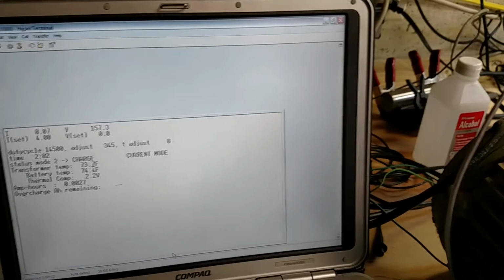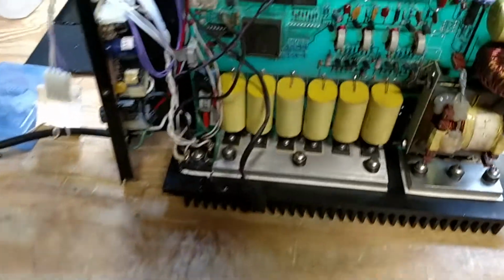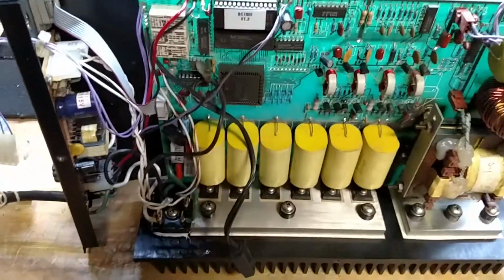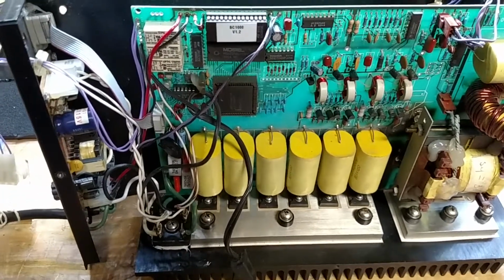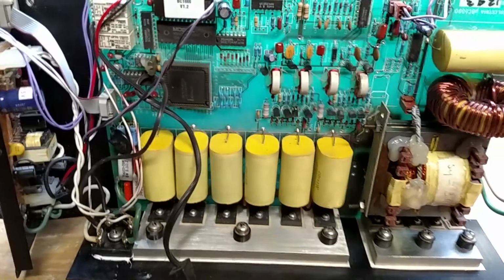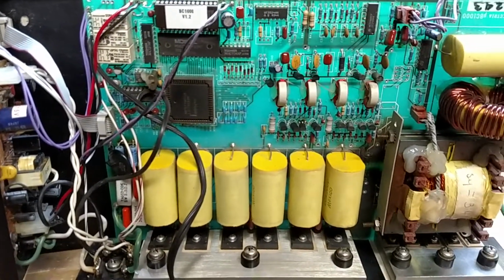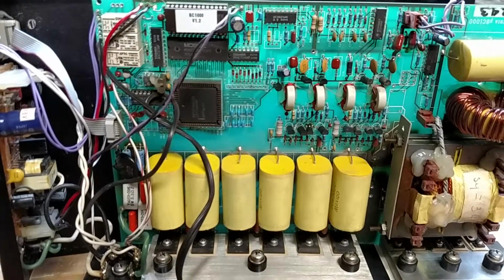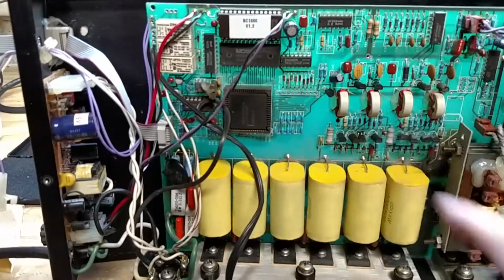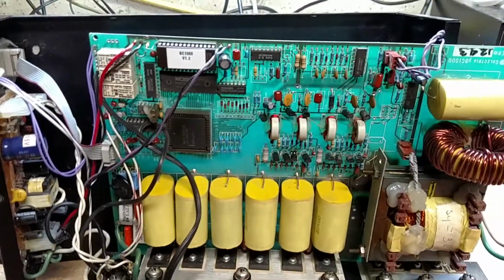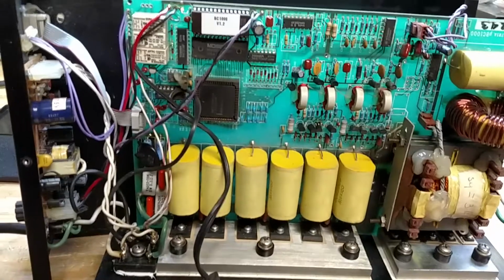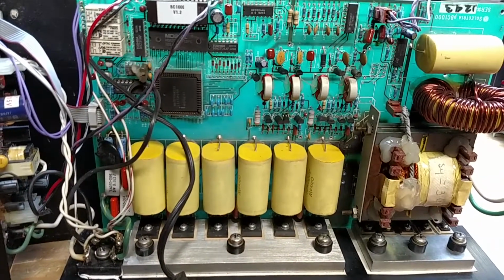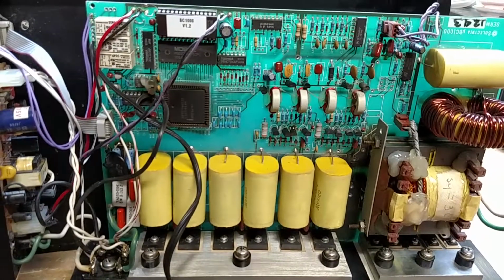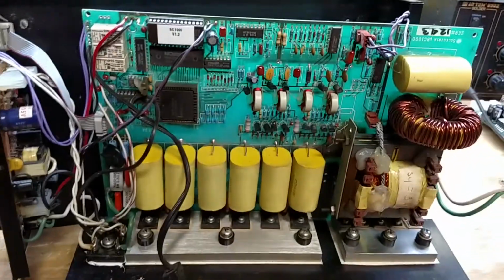So, as I suspected, at least we're talking now. Before we had no communications because there was no EPROM. So we're reading the code right now. But we have to do some more troubleshooting. We're powering it, everything's working, but we're not getting any oscillation. The transformer's not right, or the oscillator, something in here is probably dead. So we'll just have to look into it and do some troubleshooting. I don't see anything obvious. Nothing's smoking or anything. Or I've just missed something really simple.